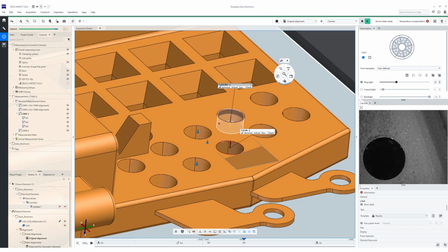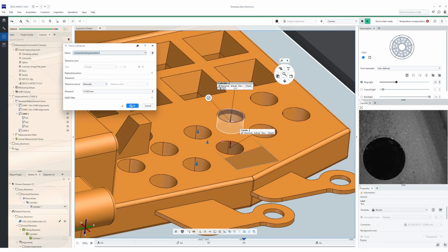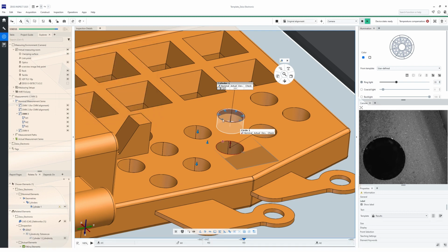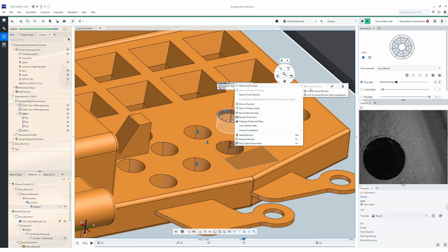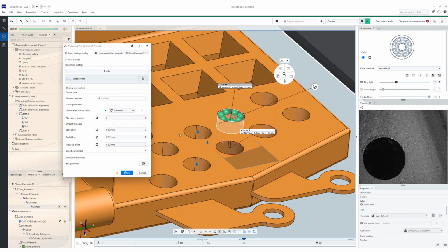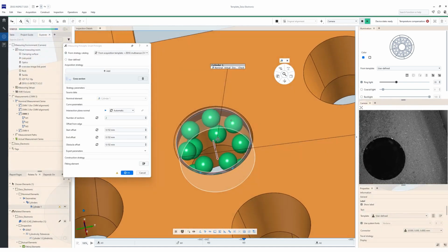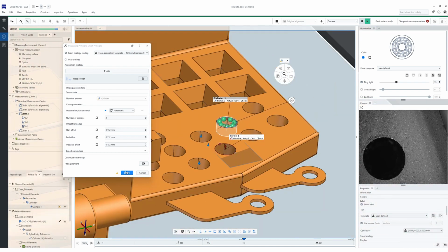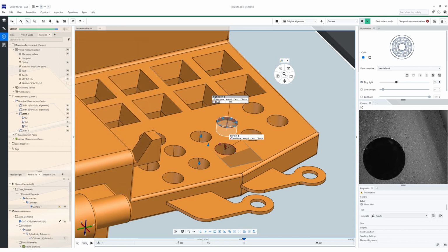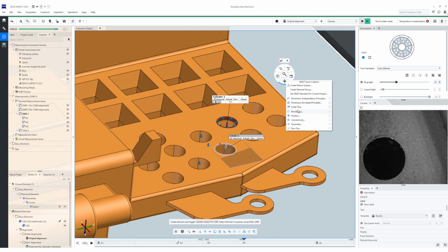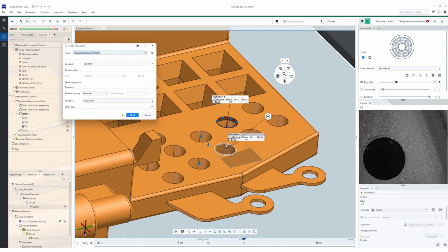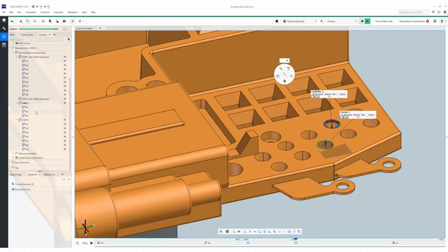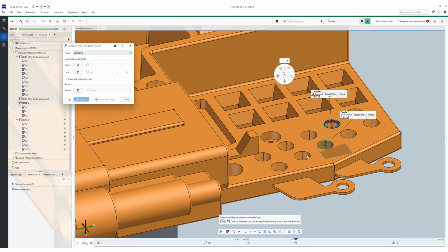You can visually see the generated points, and in this cylinder, you can observe the effect of the measuring principle based on the defined characteristics. For example, if we request a measurement of cylindricity, the software will scan the cylinder at different heights. The same counts for elements measured optically, like a request on roundness for a circle. If we change or add an element with a defined characteristic, SmartTeach will also automatically update the generated paths and everything connected to that element, ensuring that changes to the project are reflected seamlessly.